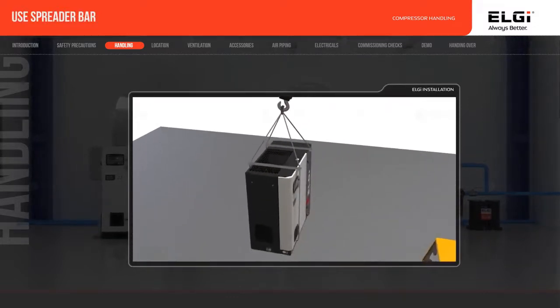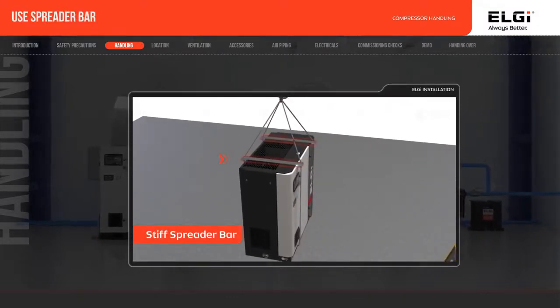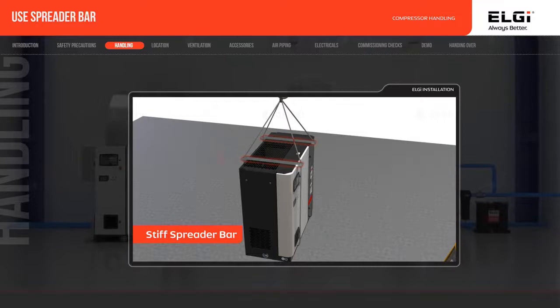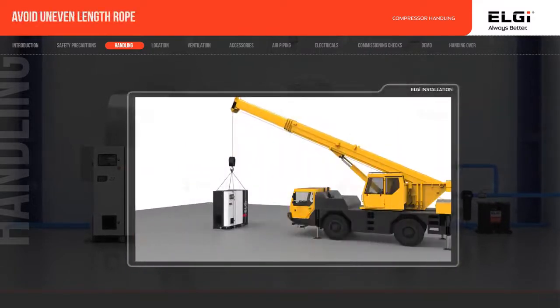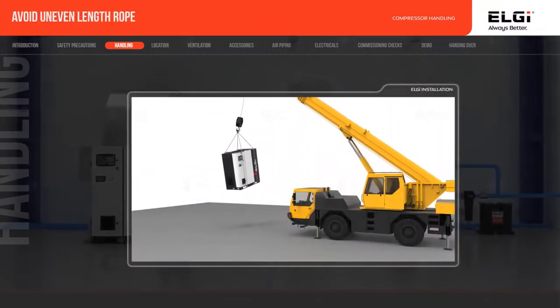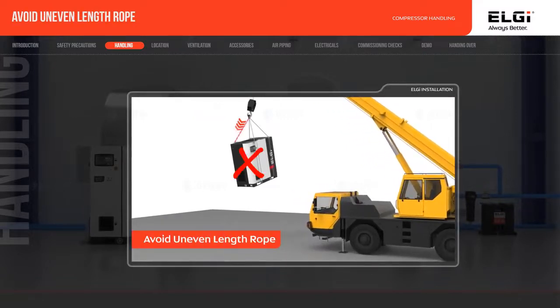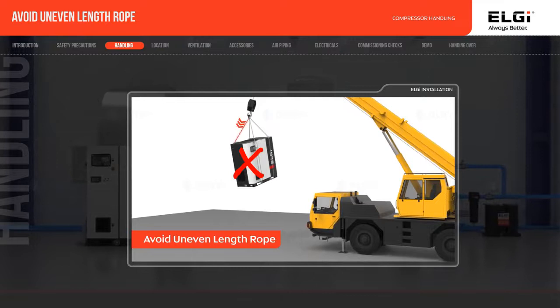If you are using a crane, use a rope or belt with a stiff spreader bar to distribute the load equally. Also, this will increase stability and decrease the load applied during hoisting. Avoid using an uneven length of rope or belt while lifting the compressor, to prevent rope or belt slings from damaging the compressor canopy.